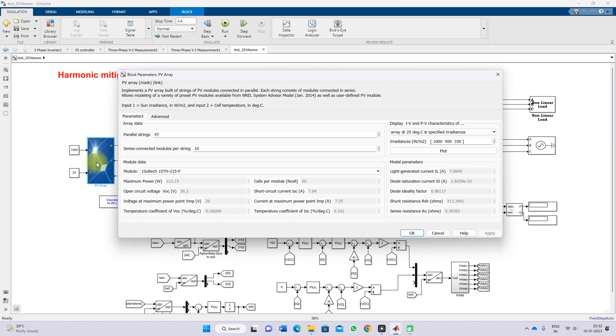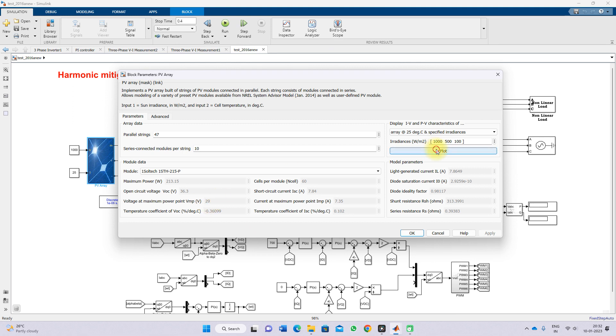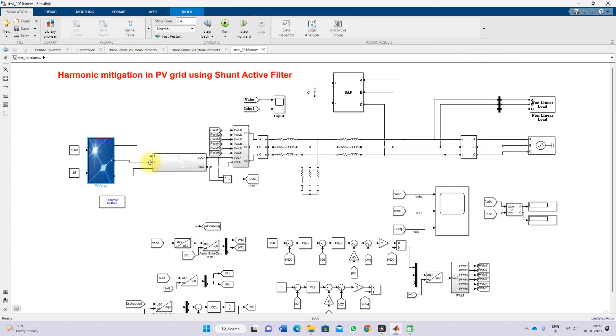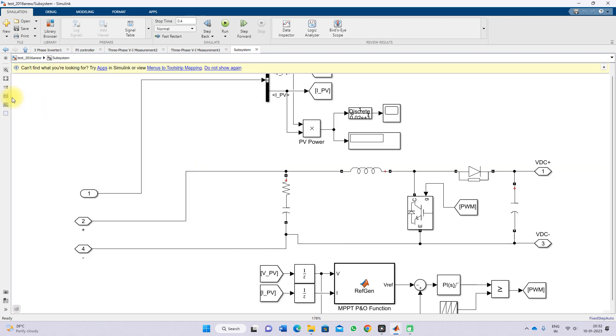The PV array rating is 100.2 kilowatts. Here we are using 47 power strings, with each string having 10 series-connected modules. A single panel's maximum power is 213.15 watts and the voltage at maximum power point is 29 volts. This is the IV/PV characteristic of the PV array, and it will be connected to the inverter via the boost converter.